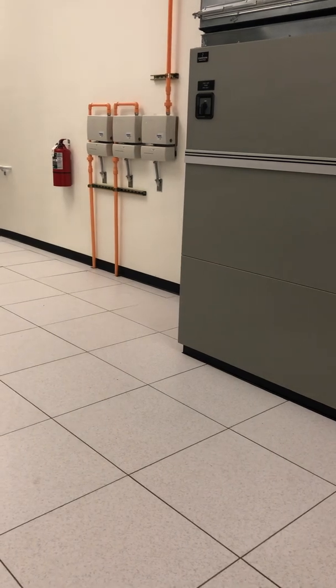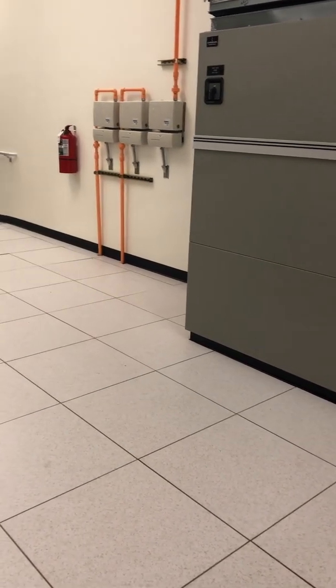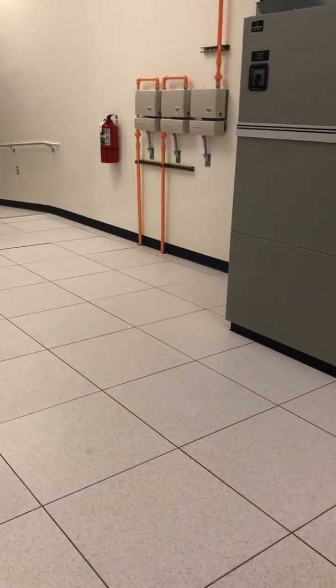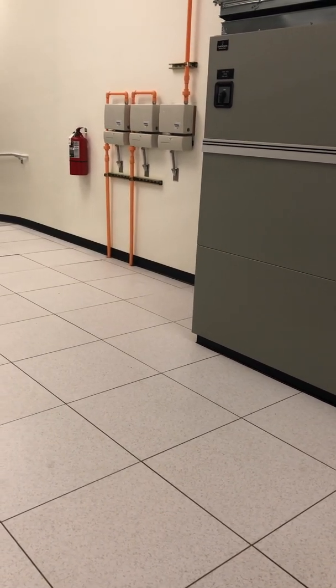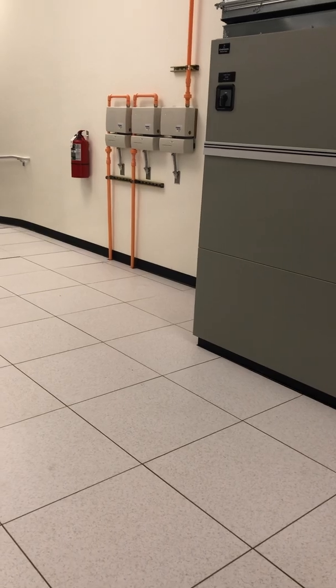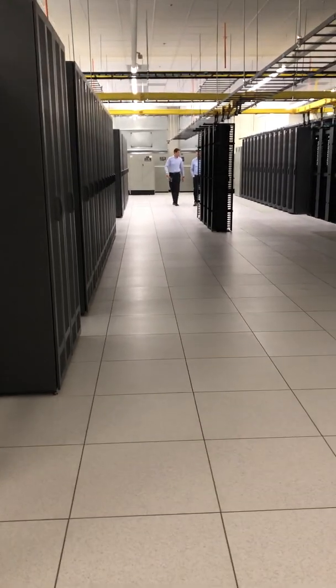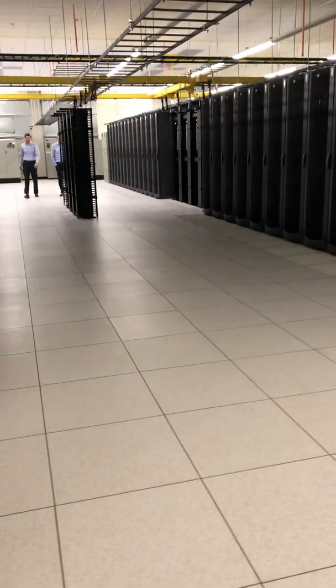So there are a few little things. You need a coat of paint here, shampoo the carpeting. There's nothing functionally wrong with the site. The only single point of failure that we've seen is the power. It's basically the attachment to the outside utility going through a single generator and a single switch. There are some improvements I would have considered if I had more money. They wouldn't be that involved and are certainly still on the table.